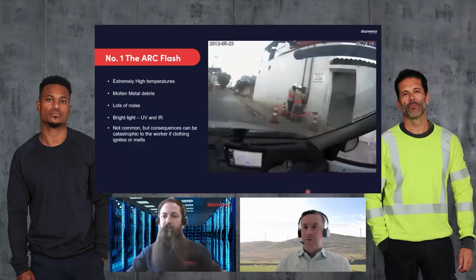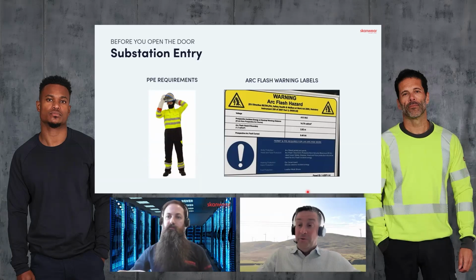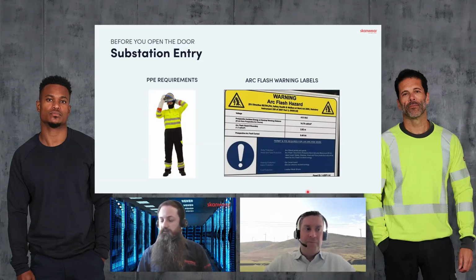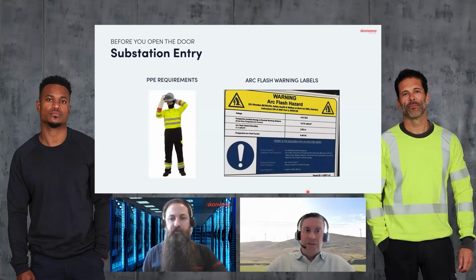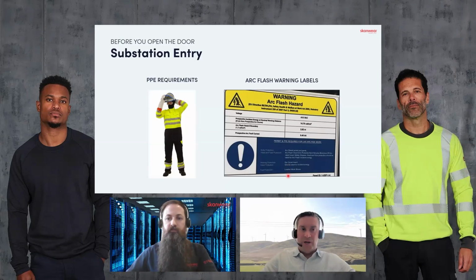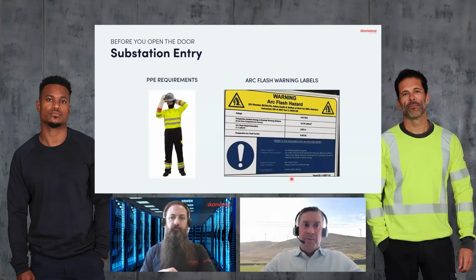Rolling back on that slide from Dan — there might be a lot of people who haven't had an arc flash survey done to establish the incident energy, so you could be walking into a bit of an unknown. You're not on your own if that's the situation on the sites you work on; I know there'll be plenty like that. So it's about making sure you've got some system in place to understand what levels of fault may occur within that substation. It goes back to what Dan mentioned about knowing where you'll actually be working, doing that pre-work check maybe a couple of days before if you know work's coming up, to assess the hazards. And if a site hasn't got an arc flash energy study, make sure you find out what you need to do to know what protection requirements apply.